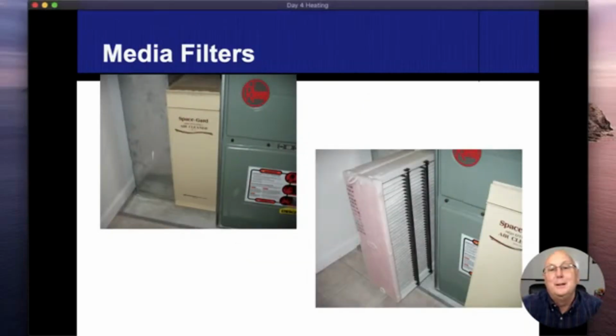These cartridge filters that we're seeing more and more of, they're higher MERV. I'm hearing these things go for 6 months to a year. And I'll let them run until I get a bad temperature rise out of these things.